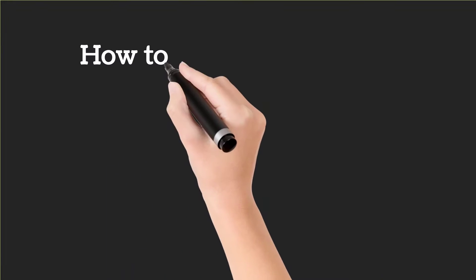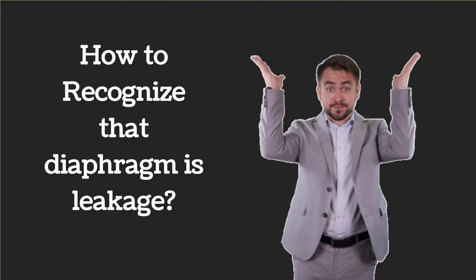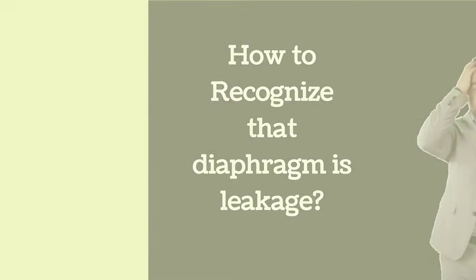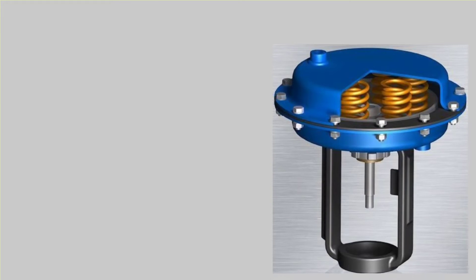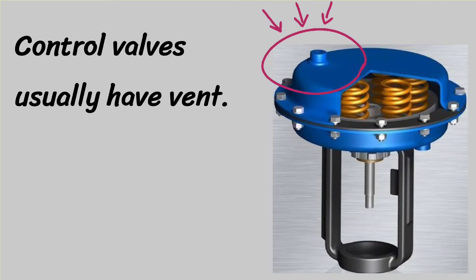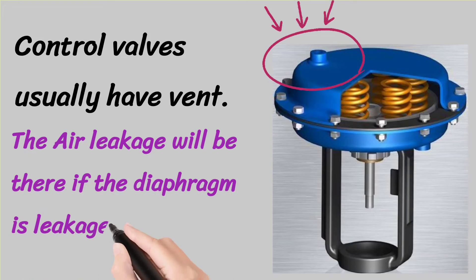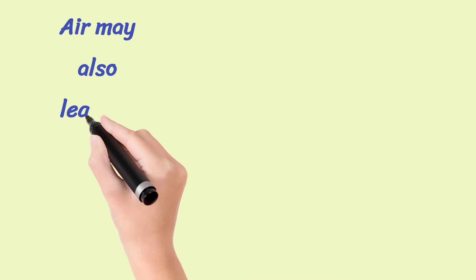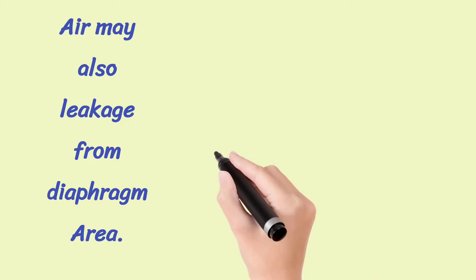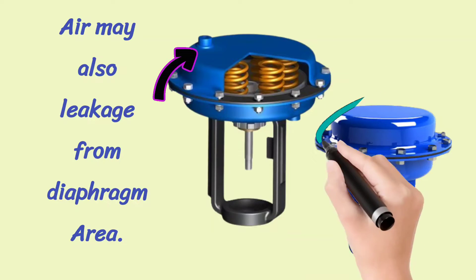Now, we will see how to recognize that control valve diaphragm is leakage. Control valves usually have a vent. You can see this by the circle shown. If the diaphragm is leakage, air leakage will be there from this vent. Air may be leakage from the control valve diaphragm area, as shown by the arrow and the circle.